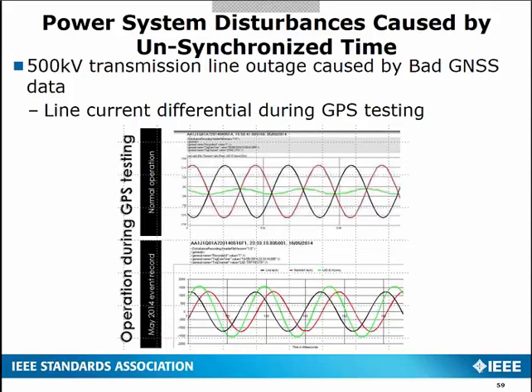But when the one satellite incorrectly synchronized to the one GPS receiver, the differential relay was incorrectly synchronized to the satellite under test. It shifted the signals by 70 degrees, putting them at 110 degrees out of phase with each other, creating a much larger differential current. And this caused not just one 500 kV transmission line to operate on our system, but two 500 kV transmission lines operated over the weekend.